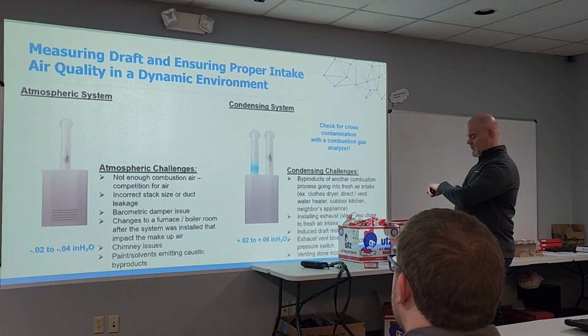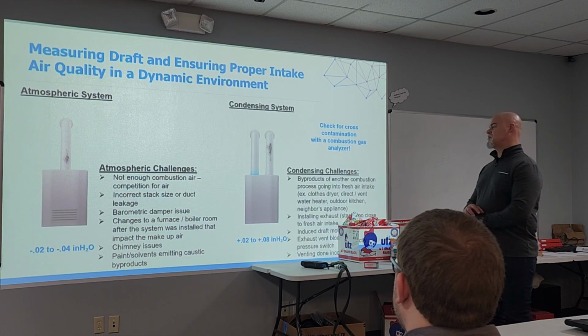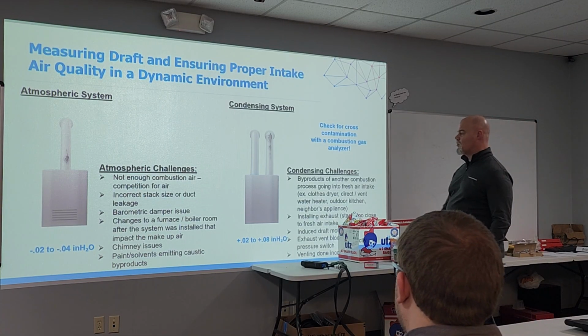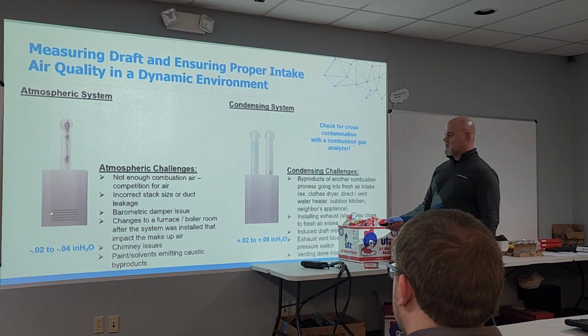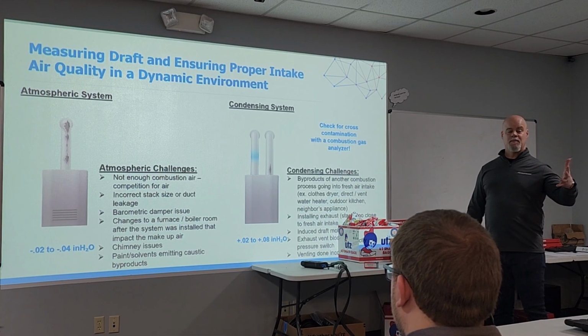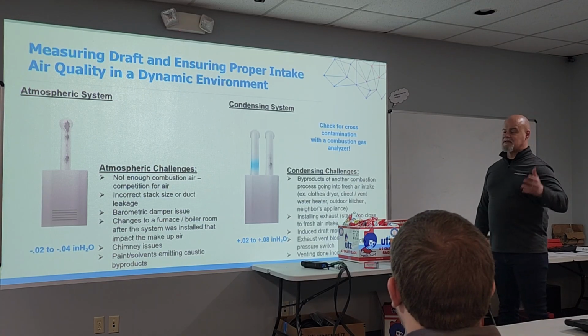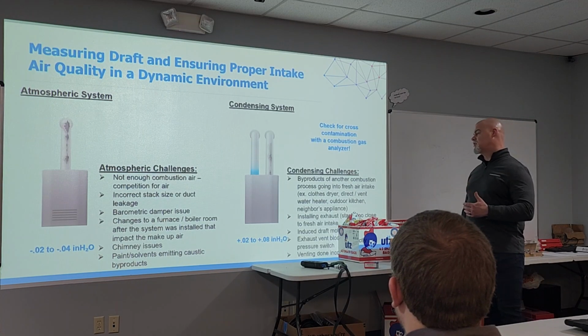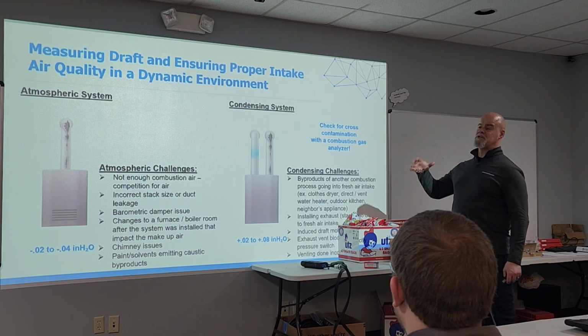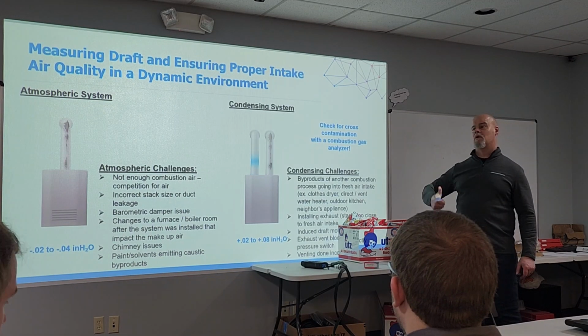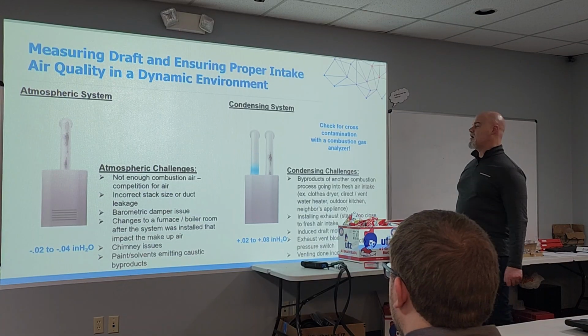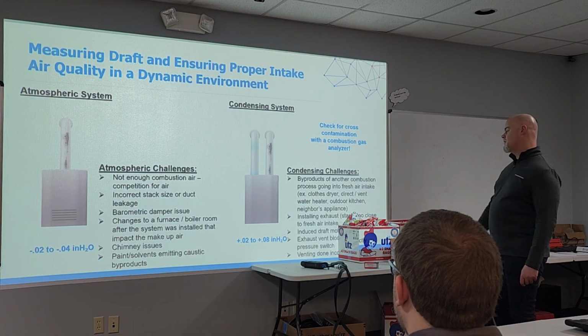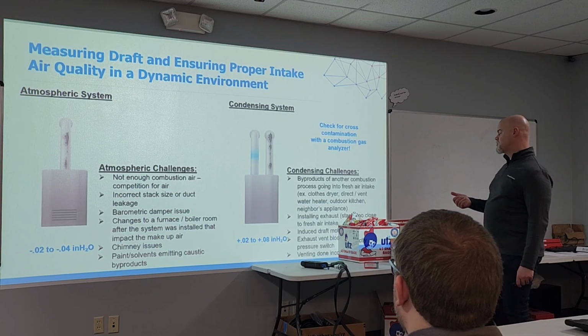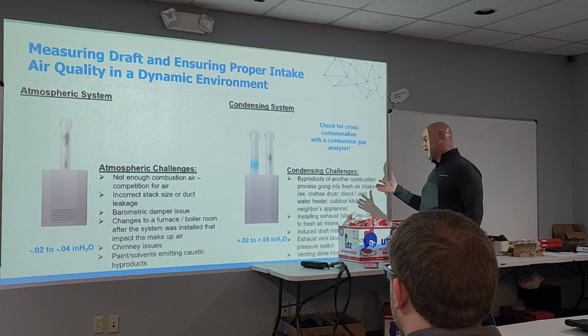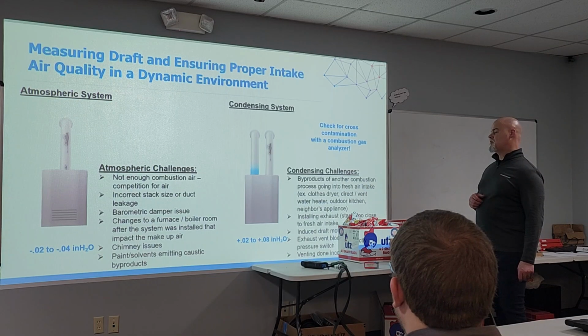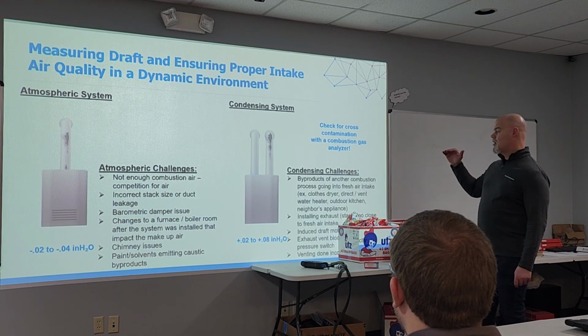Draft testing. Yeah, for time, we're good. So we have two different kinds of systems here, as you can tell. One atmospheric, one condensing. As I mentioned before, this is pulling air from the room that it is using for its combustion process. So we can have competition for combustion air. We can have incorrect stack size. We can have leakage. We can have a damper issue. We can have a chimney issue. We can have somebody who changes a furnace or boiler room and removes a louvered door and removes a drop ceiling, which will choke the system off for air. That's an issue. Over here on the condensing side, we can have an exhaust vent blockage. We can have a pressure switch misbehaving or not functioning correctly. And we can also have a draft inducer or induced draft motor misbehaving too.